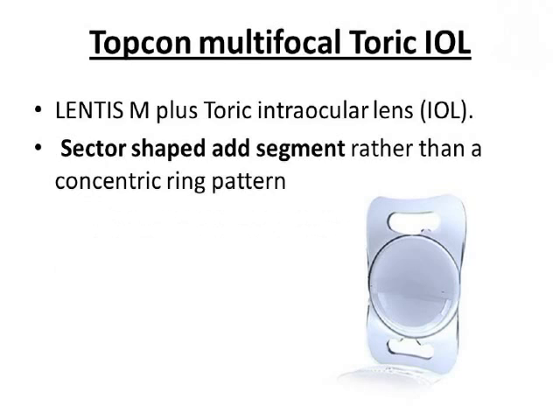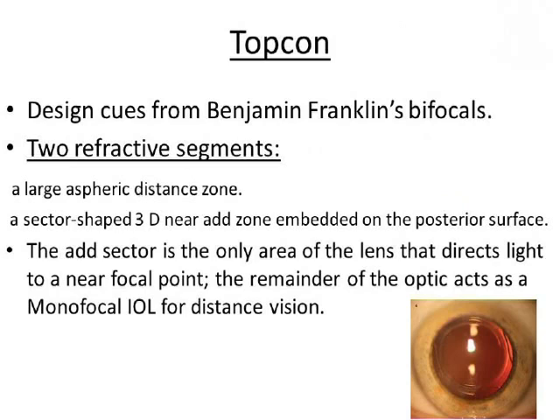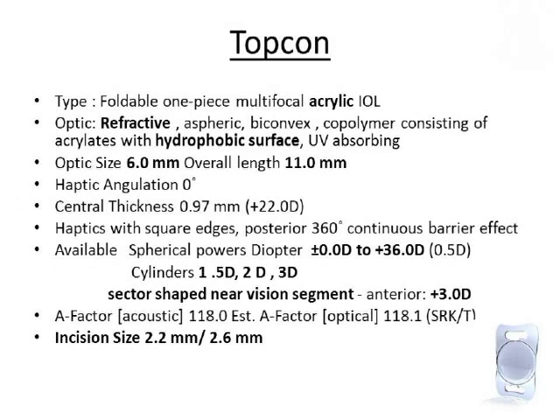The Topcon multifocal toric IOL, unlike the concentric ring pattern, has a crescent-shaped add segment — an idea taken from the bifocal glasses of Benjamin Franklin. It is a refractive IOL with a hydrophobic surface. The overall diameter is 11mm and the optic diameter is 6mm. It is available from 0 to 36 diopters spherical and 1.5 to 3 diopters cylindrical. It has an add power of +3 diopters and can be implanted through an incision of 2.2 or 2.6mm.